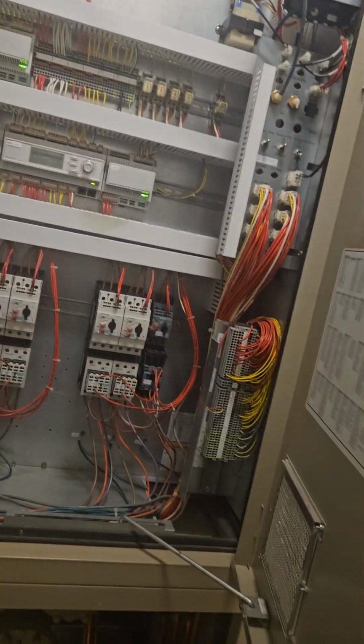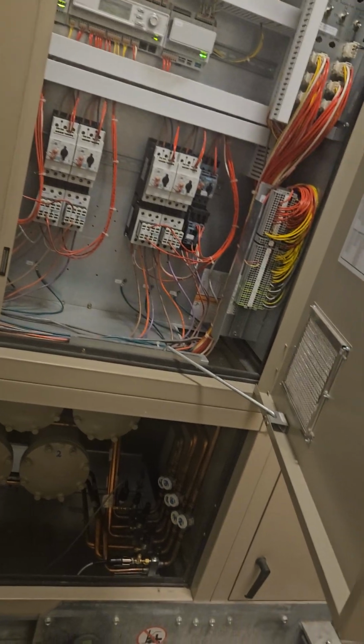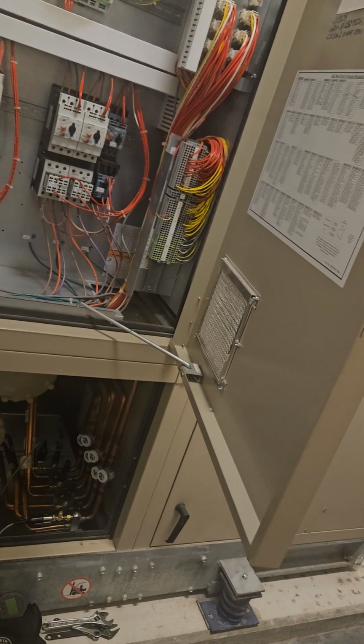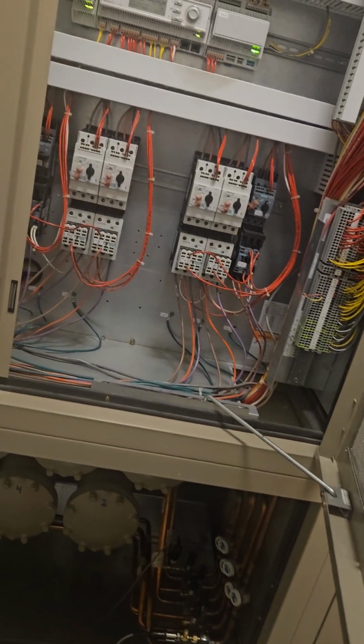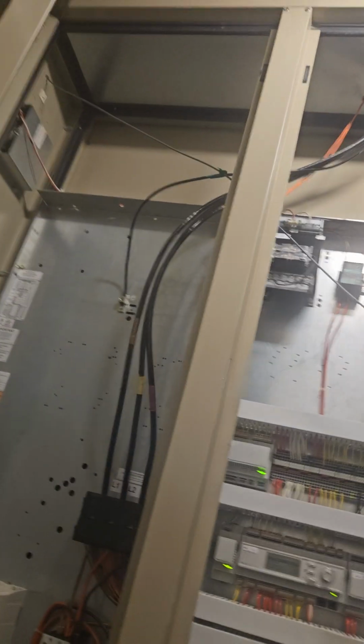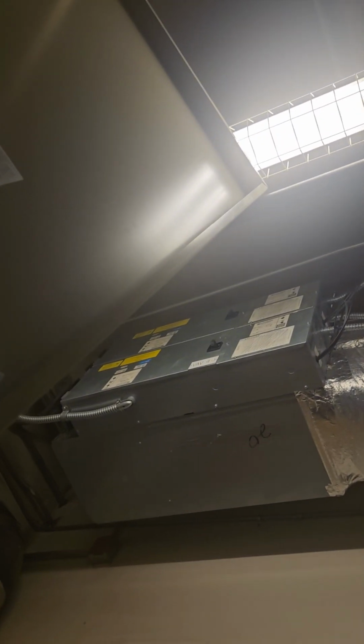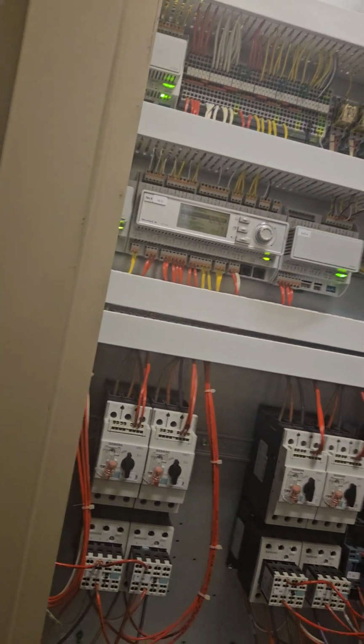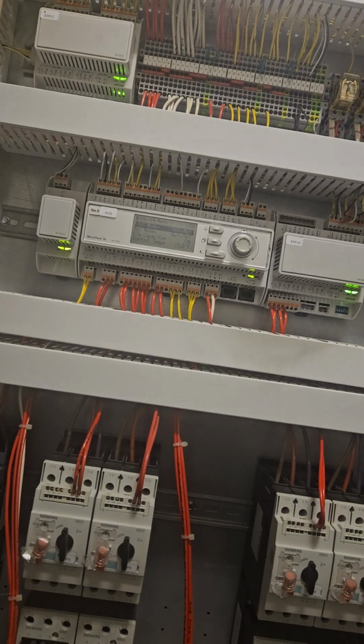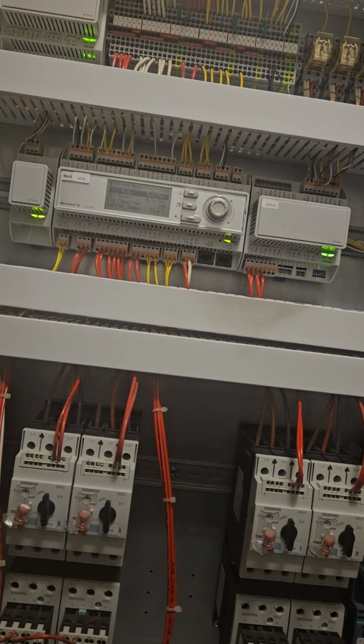I heard one just turn off, and it's kind of hard to do the PMs on these because you have to have 1 or 2 running. These type of units, and most of them like this, are on fan power boxes and VAVs. Perfect example, there's a VAV right there. So it's not like you can just crank up the blower and crank up the cooling, and, you know, there's duct static pressure, there's the whole 9. So it tends to make these things take quite a bit longer.